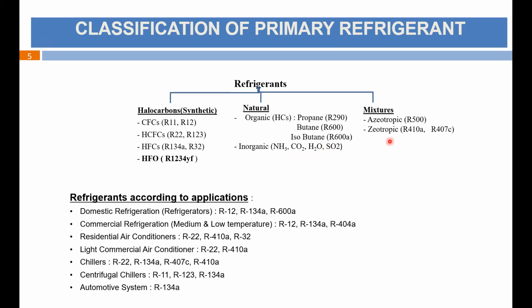Coming to the last type, which is mixture. There are two types of mixture refrigerant, that is blending of two types of single refrigerant. That may be classified into azeotropic refrigerant and zeotropic refrigerant. So R410A, which is commonly used in many systems, is a zeotropic refrigerant. I'll come to the details of this kind of refrigerant, what the characteristics of that are. R407C is also a zeotropic refrigerant.